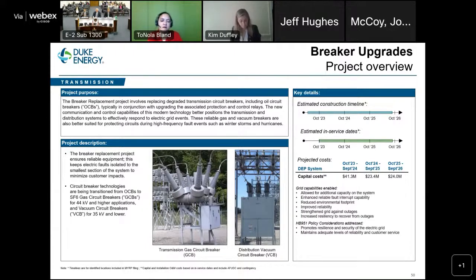Our strategy here is to identify assets that are beyond the end of useful life, that have an expectation for failure based on make and model trending that we have, based on the number of operations and the number of faults. That's data we gather. Essentially, the more a breaker operates, the more wear it is getting. We also are targeting locations based on the number of customers served and the configuration. Is it networked? In other words, is there redundancy, or is it a radial system? There is no redundancy built in.